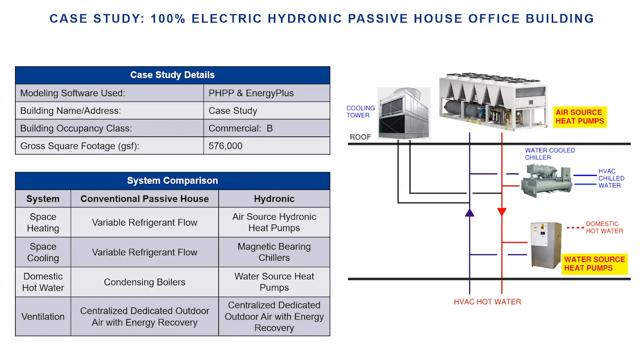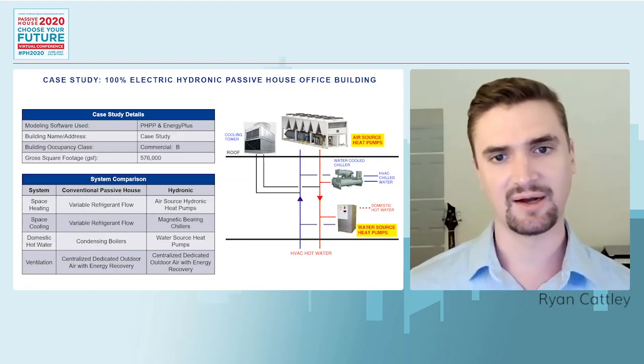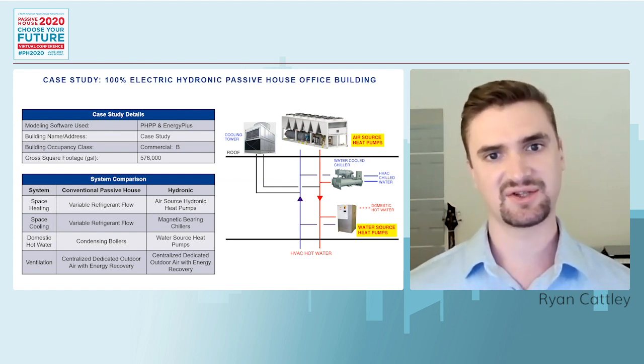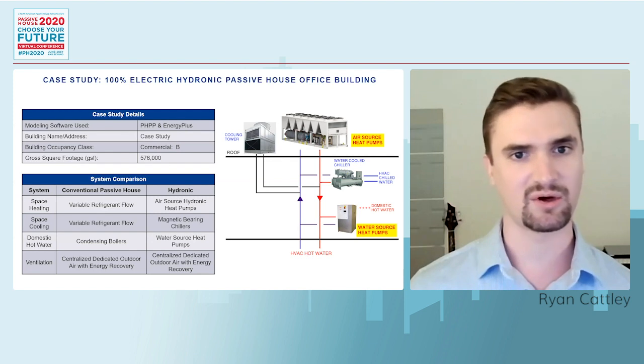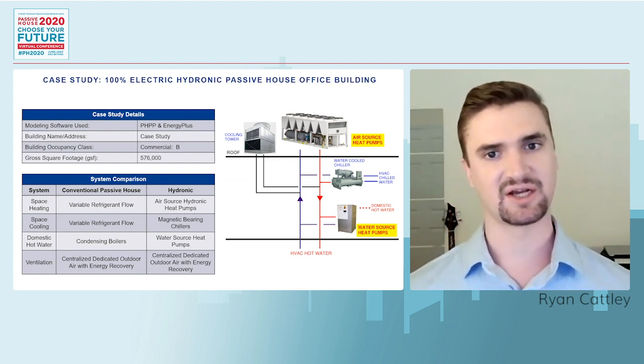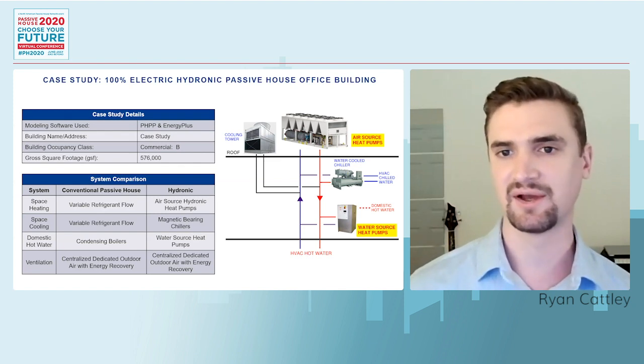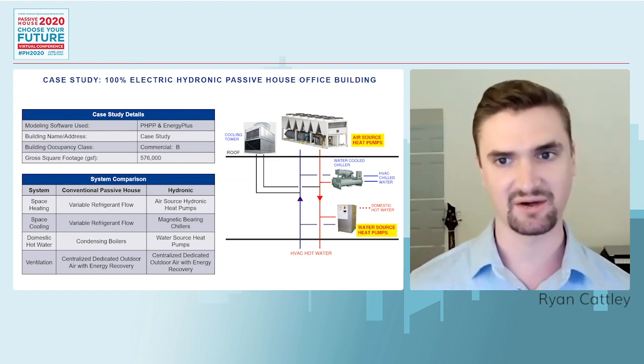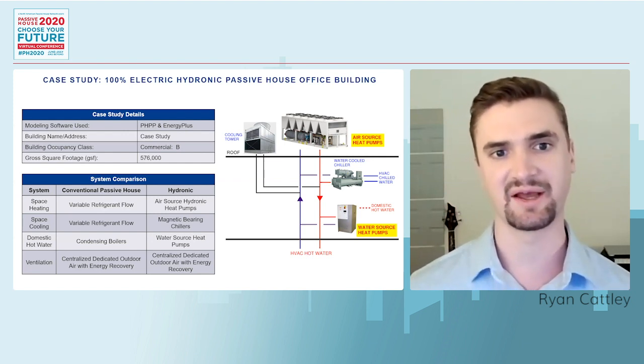And with the substitution of the boiler plant with air and water source heat pumps for space heating and for domestic hot water, it gives us an additional opportunity for heat recovery from our chiller plant. So typically a water-cooled chiller will create chilled water for cooling the building, and then it will reject heat to the outdoors through the cooling tower. However, in this case, because our air source heat pumps are operating at a lower hot water temperature, we can actually use that heat rejection, or at least some of it, to help heat our building hot water loop, to help meet our building space heating demand.